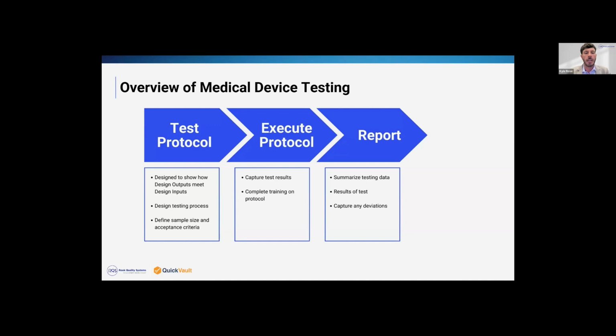A sample size can be determined a variety of ways. I think either referencing actual standards that might call out sample size or requirements, or using a risk-based approach. So identifying with your risk analysis, higher risk devices should have more testing, or higher risk features, and lower risk features should have less testing. So that's a high level scope of how to determine sample size, but there are definitely more specific ways you can look into doing sample size as well.